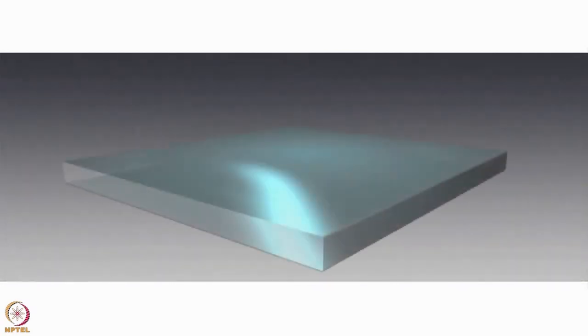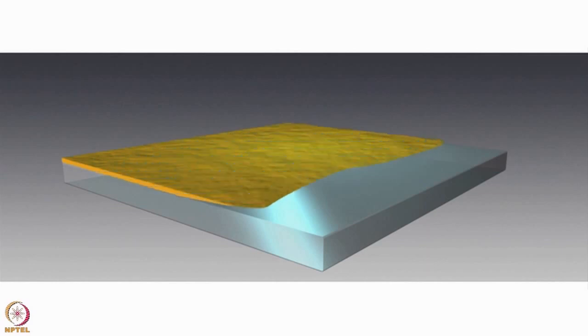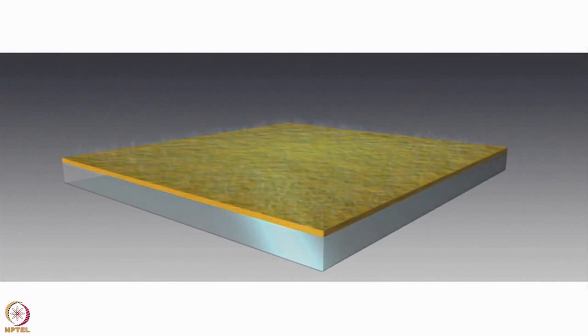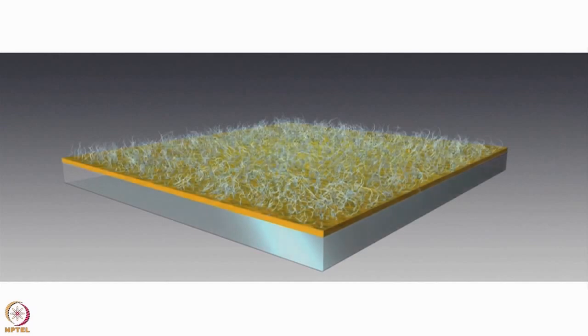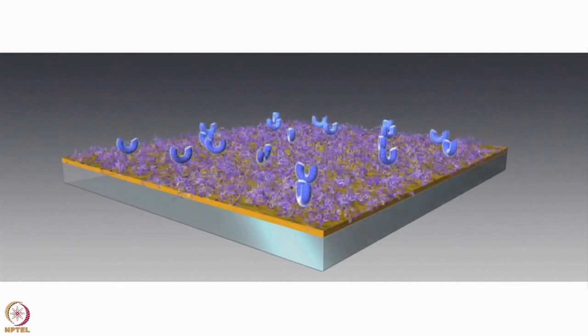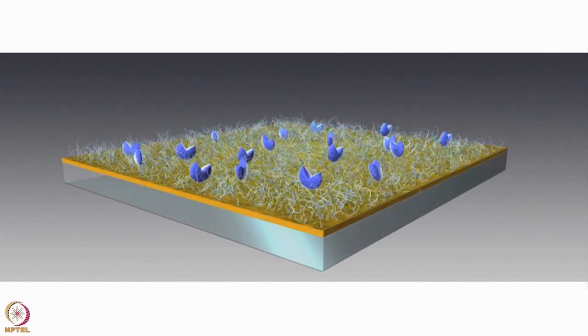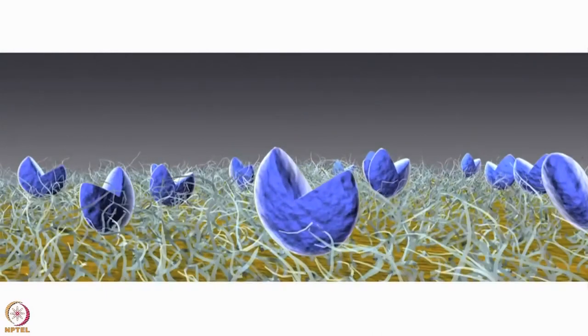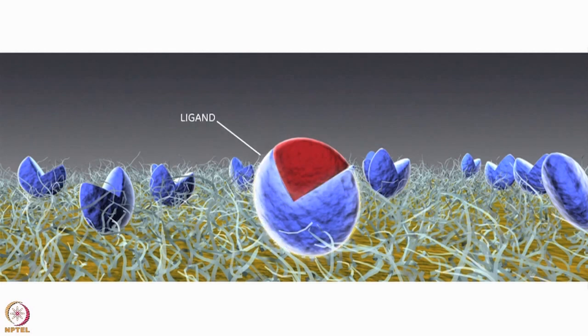A glass slide coated with a thin gold film creates the sensor surface. For most applications, a dextran matrix covering the gold film acts as a substrate to which molecules can be attached, and provides a hydrophilic environment for the interaction. Other matrices can be used to attach specific types of molecules. The specificity of the surface is determined by the nature of the molecule attached to it. One binding partner is attached to the sensor chip surface — called the ligand — and the other is injected in a continuous flow of solution — called the analyte.